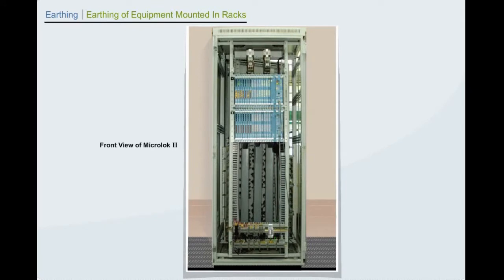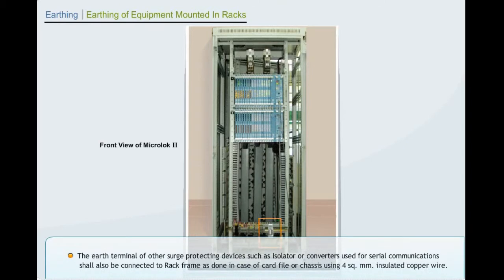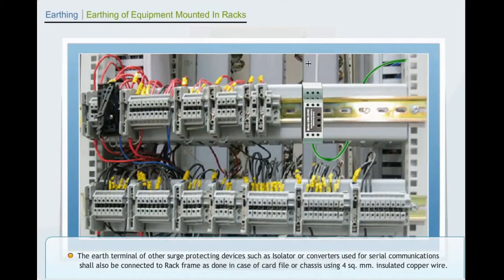When no ground studs are provided on the card files or chassis, ensure good contact between the metallic mounting ears of the card files or chassis and the rack using proper mounting screws and star washers. The earth terminal of other surge protecting devices such as isolator or converters used for serial communications shall also be connected to rack frame as done in case of card file or chassis using 4 square mm insulated copper wire.